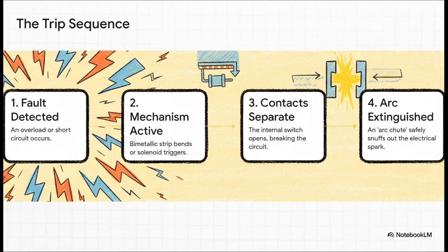So let's put it all together in the trip sequence. A fault happens. Either the bimetallic strip slowly bends from heat, or the solenoid instantly triggers from a magnetic surge. Either way, that action forces the internal electrical contacts apart, breaking the circuit. But here's the really cool part that most people don't know about.